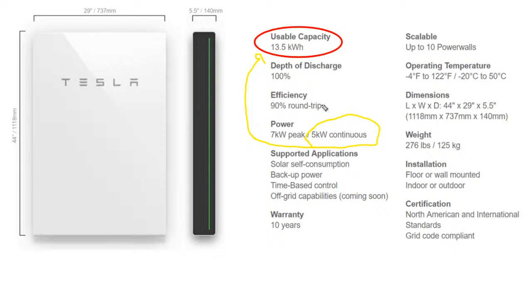That actually makes a designer's job a lot easier, because if I'm designing a critical load panel, I know that the maximum load for the panel should be 5 kilowatts or so, maybe slightly more since all the loads aren't going to be on at the same time. In our smart home load control class, we talk about how you can use wall plugs and stuff like that to extend how many devices you can plug into this backup power. But that means my critical load panel would have about 5 kilowatts worth of devices on it, and if all of those devices were on at the same time, it would run for at least 2.5 hours, maybe longer. So maybe you could get 5 or 6 hours of capacity if the devices are running at a 30% utilization rate.